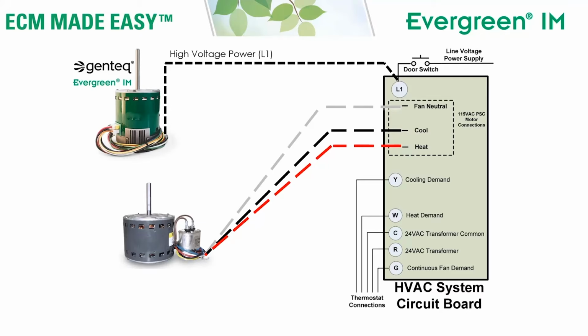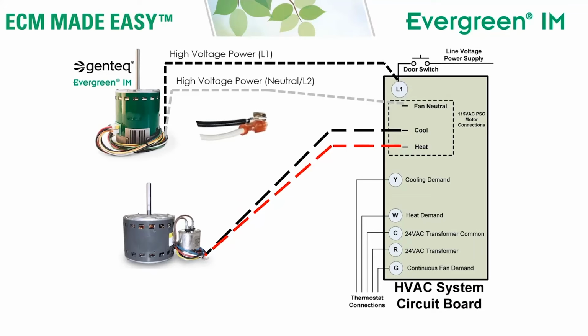either directly from the door switch or from the main disconnect. Next, we're going to remove the neutral wire from the old motor, and connect the neutral wire from the Evergreen IM motor. Now, if we were connecting this to a 230 volt system, we would connect that white wire to the L2 side of the power supply. For those two connections, the black and white high voltage power wires already have their 1/4 inch terminals built onto the leads. In fact, the black wire has a piggyback, so that you can disconnect the wire that was on the L1 terminal at the circuit board, connect it on the back of the piggyback from the Evergreen IM harness wire, and put it back on the board.